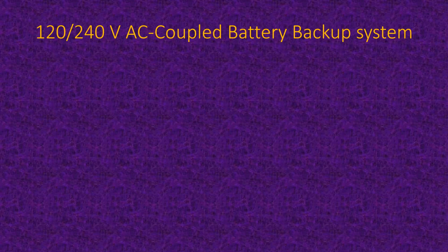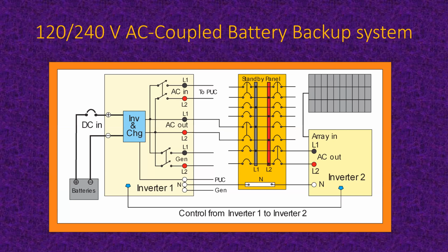Now here's a 120/240 volt AC coupled battery backup system. We've been doing DC coupled stuff. Let's take a look at an AC coupled schematic. And again, here's your inverter number one. That's the DC, the battery backup type inverter. You see the batteries are there and they connect directly to the inverter. No array, no charge controller, anything connected to that inverter. The array is connected to the other inverter, which is a straight grid connect inverter. Now let's look at some of the possible operating conditions for this. Let's say that it's daytime, the solar is running, the utility is up, it's just kind of like a normal day. So that means that the PUC is the point of utility connection. Power flows in either direction from that point.